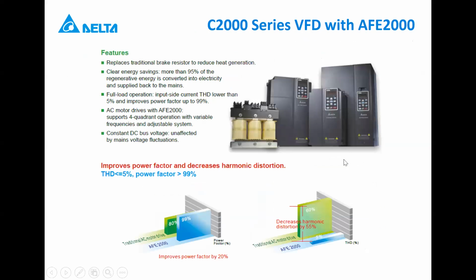With the AFE 2000, other than better harmonics and better power quality, it helps replace the traditional brake resistor. It reduces heat generation, which prolongs the lifespan of your VFD. Also, since you don't need to use as many brake resistors, you save cost. With the AFE, you can support 4-quadrant operation with variable frequencies and an adjustable system, plus a constant DC bus voltage.